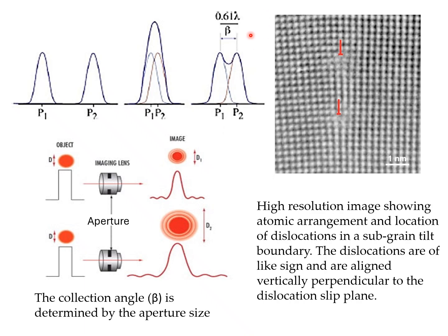The resolution limit is not dictated necessarily by the width of this peak, but by being able to distinguish, when you have overlapping peaks, what is the minimum separation that one can tolerate, where we can still distinguish between these peaks. And that's the expression that dictates this resolution limit: 0.61 times lambda over beta, where beta is the semi-angle of the collection angle of the aperture.